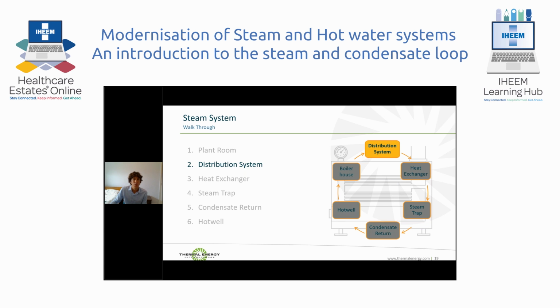That steam is then reduced at the point of use through a pressure reducing valve and a control valve for the individual heat exchanger. The advantage of this is that it increases the dryness as we reduce the pressure of the steam, and also increases the amount of latent energy. Counterintuitively, with steam, the lower the temperature and pressure that you consume the steam, the more energy per kilogram you get out of it. This is because we're actually using the latent energy rather than the temperature to drive the heat used.